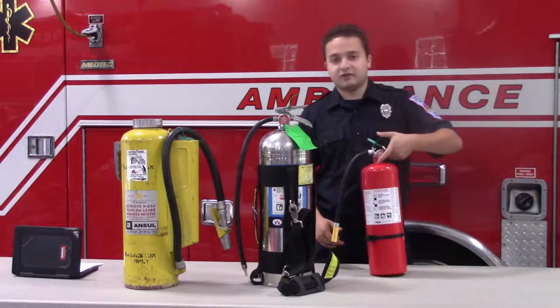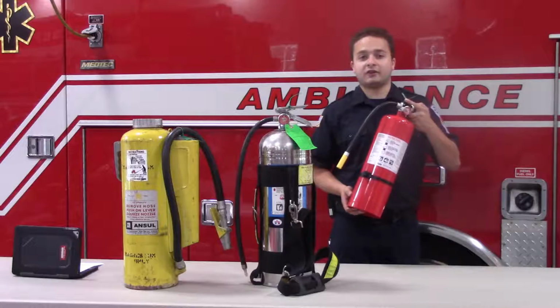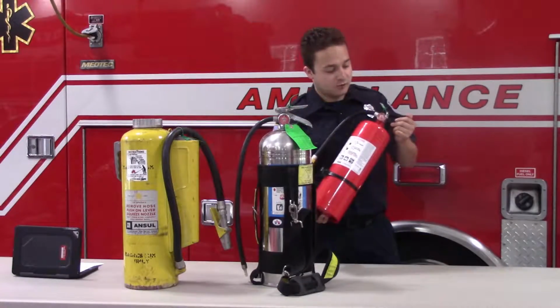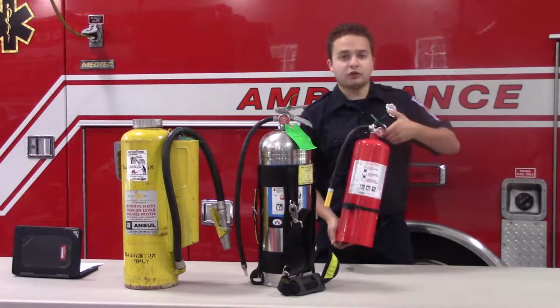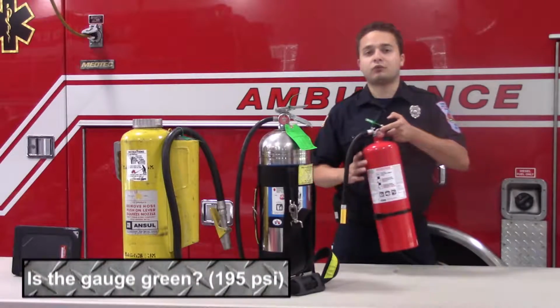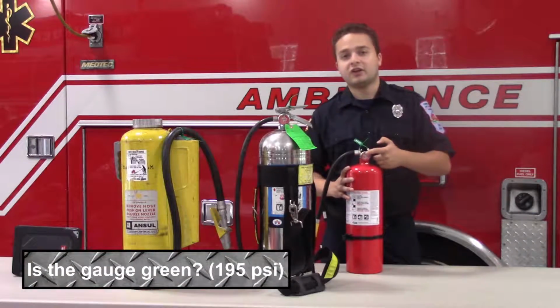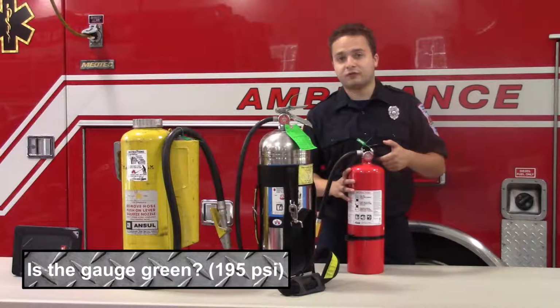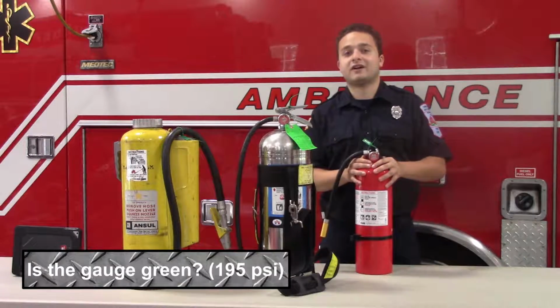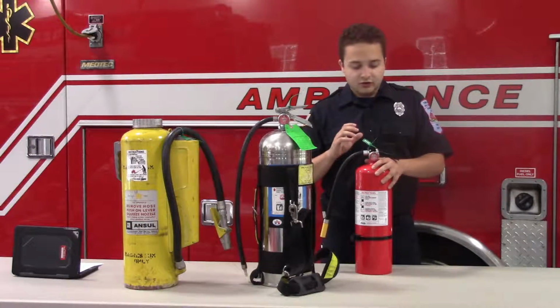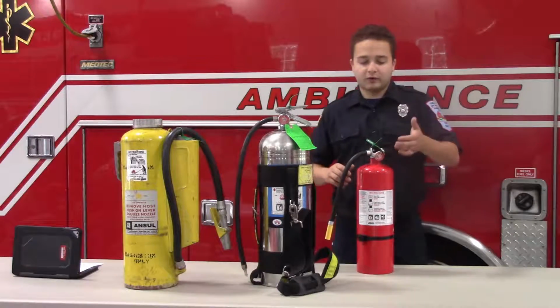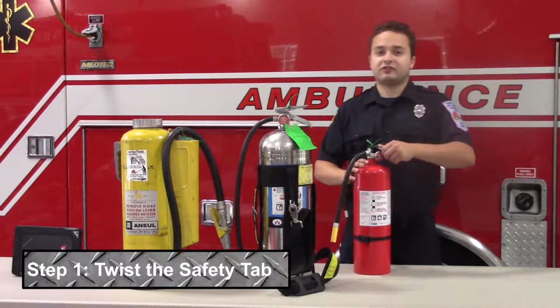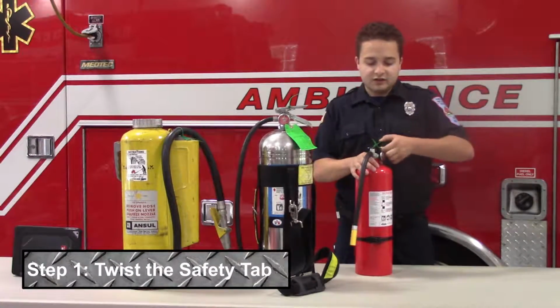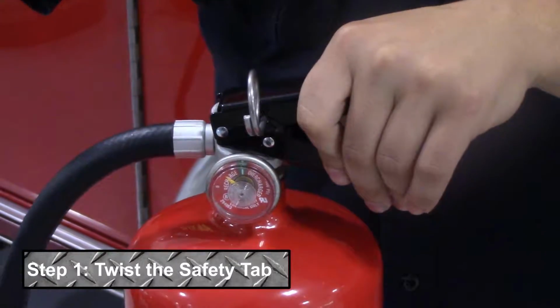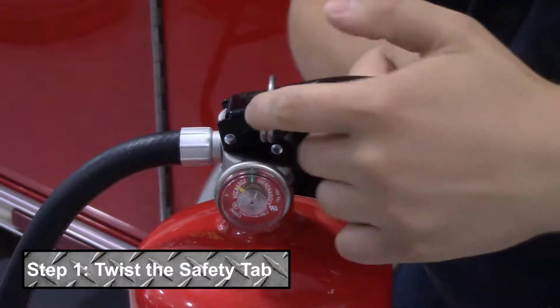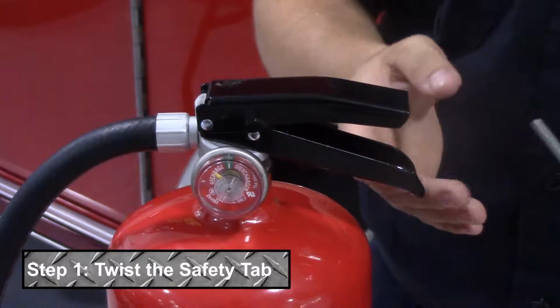So the moment we've established what type of fire it is and gotten the right extinguisher, we're going to take a quick look and check the gauge. Make sure the gauge is in the green section, which means it's pressurized to the right pressure, which for ABCs is 195 psi. Now we're going to pop our safety tab off by simply turning our pin and popping it off. It's just a small piece of plastic that easily pulls off. We're going to pull our pin.